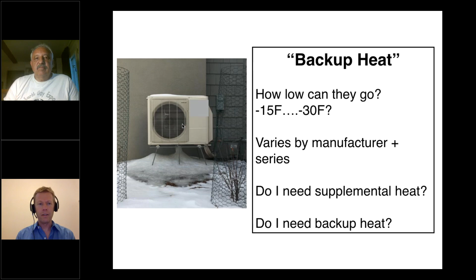This particular heat pump that's in the picture is installed in Minnesota in a 100-year-old house that's gone through a couple of very deep super insulation retrofits, but it's a 1.5 ton nominal heat pump. This model, to everyone's knowledge, has no known lower limit. During the polar vortex a couple of years ago, it was still running at minus 28 degrees Fahrenheit on January 30th in 2019. It wasn't designed to heat the whole house at that temperature, but it did keep a 3,000 square foot house above 50 degrees on those couple of polar vortex days without any supplemental heat while the owners of that house were away on vacation. So that's really cool.